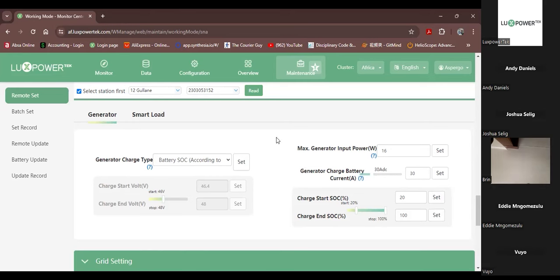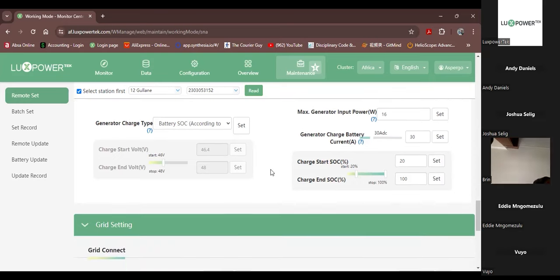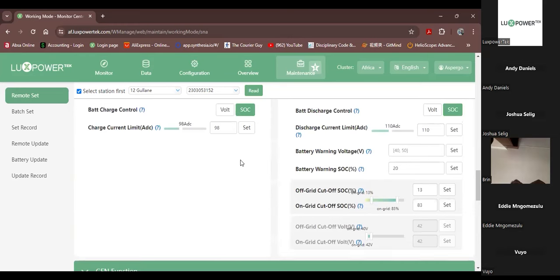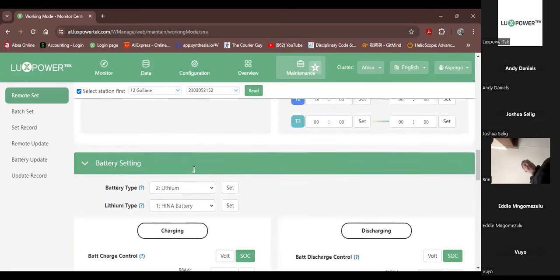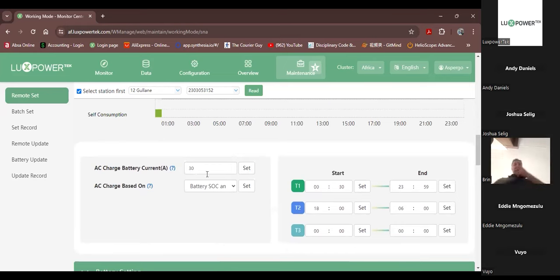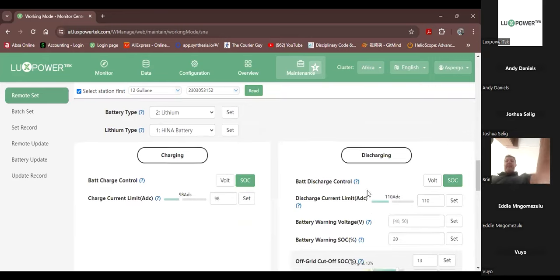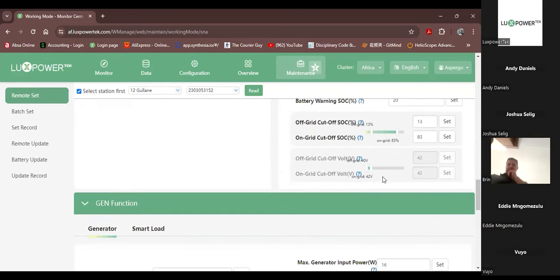But the safety feature, when you're running a generator, PV will charge. When PV is available, it will charge the batteries, and the generator will take the load as well as charge the batteries if required. Okay, so here you can set your generator charge current, and remember that this is in amp DC. Always take note of the amp. If it's 30 amp like we have here on the AC charge, then it's current in alternating current. But if it's DC, then we will notate it with a DC symbol like this here.